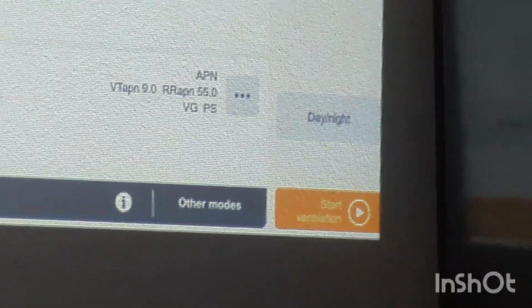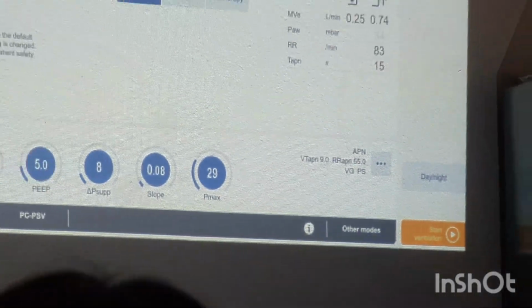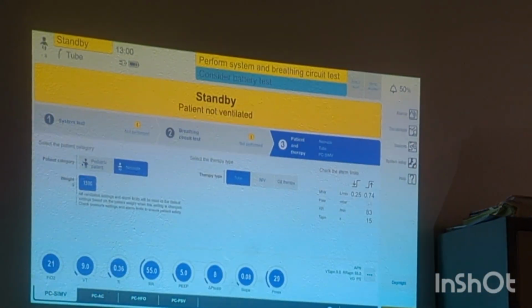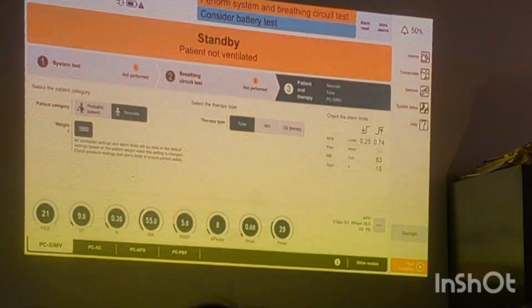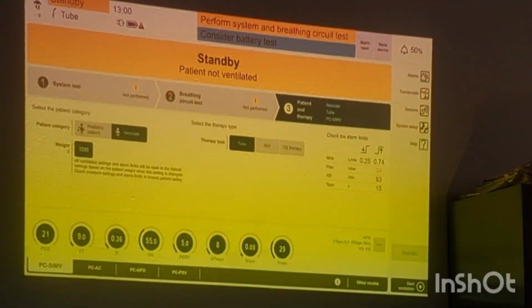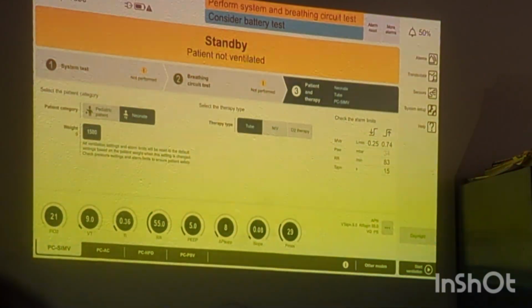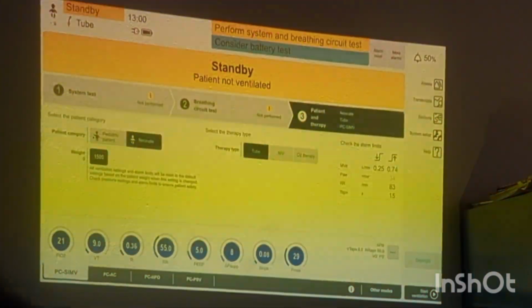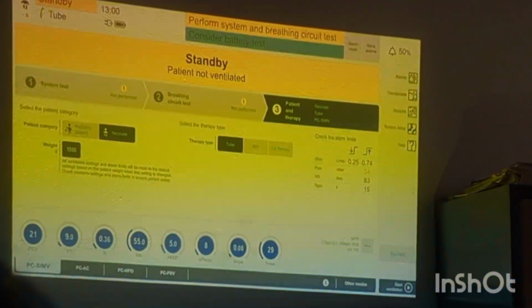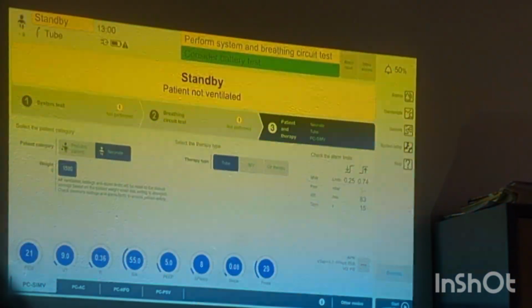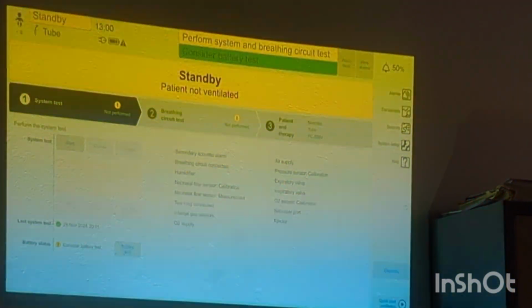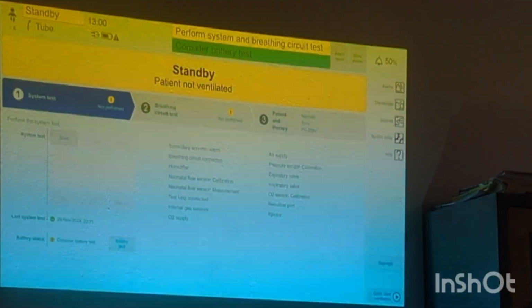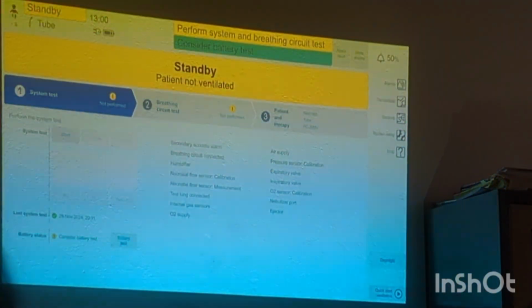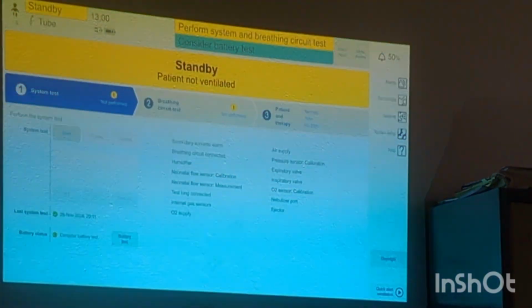You can just click and do the minimum settings. You can see it is skipping the breathing system test and also the system test. It will go directly to the patient, with the bare minimum parameters: the therapy settings, patient category, weight of the patient, and whether you are going to NIV or a tube or O2 therapy. So you can directly start the ventilation. But if you have time, what we normally recommend is, if you know the patient is coming, you should be ready, do all the system tests and keep the device ready.